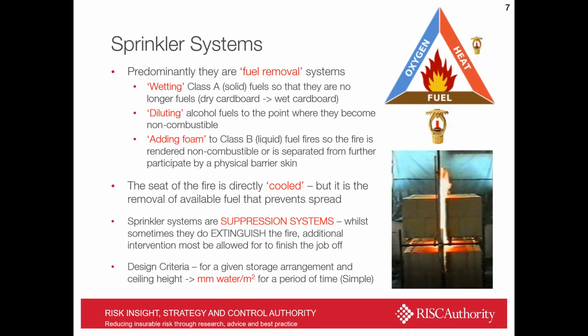But we need to be clear about our terminology with all systems as to whether they constitute suppression systems or extinguishing systems. There's a lot of confusion over the word suppression. Sometimes it's used interchangeably with the word extinguishing system as well. But for the sake of this talk, let's be clear. Suppression means that the fire isn't assumed to go out. It is meant to be constrained and held to a size, but then there will need to be a third-party activity to come and finish the job off, which commonly for sprinkler systems will be the fire and rescue services, in that the sprinkler system in actuating will have made the building structurally safe, constrained the fire to a manageable size so that it is still appropriate for approach by the fire service with their type of equipment and PPE.